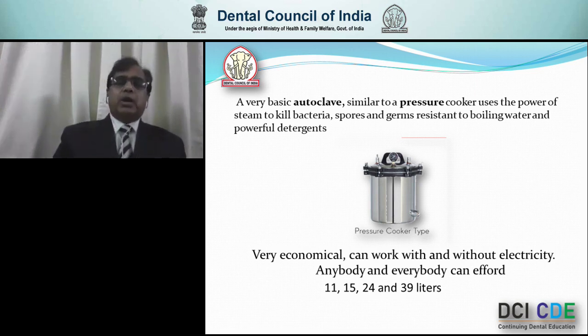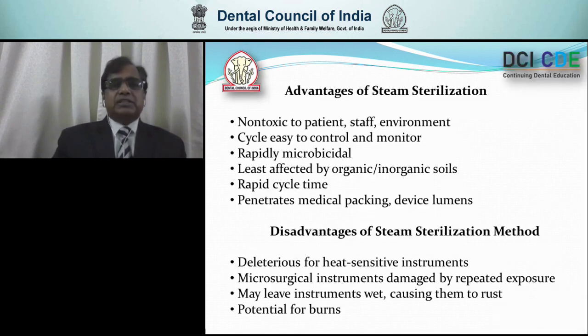The only little problem with this type of autoclave is that sometimes your instruments or drapes come out wet after sterilization. Advantages of steam sterilization: non-toxic to the patient, staff and environment, easy to control and monitor, rapidly microbicidal, least affected by organic and inorganic soils, rapid cycle time, and it penetrates medical packing and device lumens. The disadvantage is that it is heat sensitive, but during this COVID period, I advise everyone to sterilize even their scissors with steam sterilizers or autoclaves.